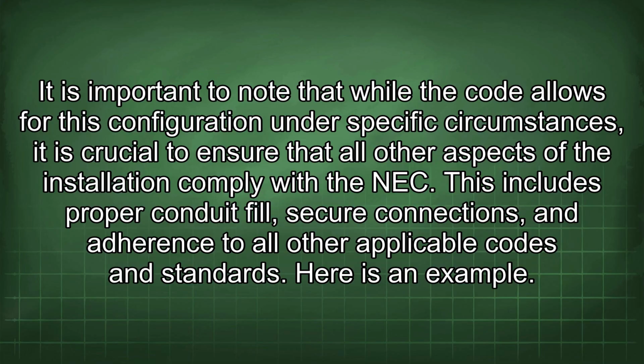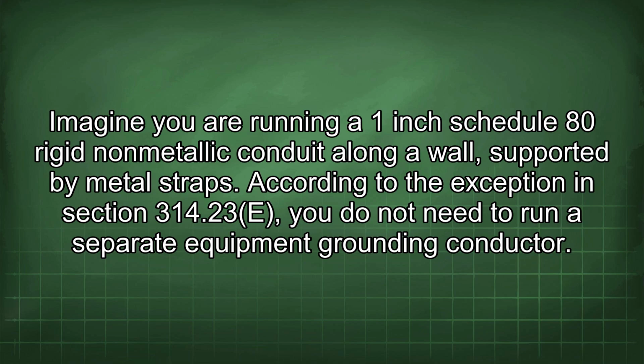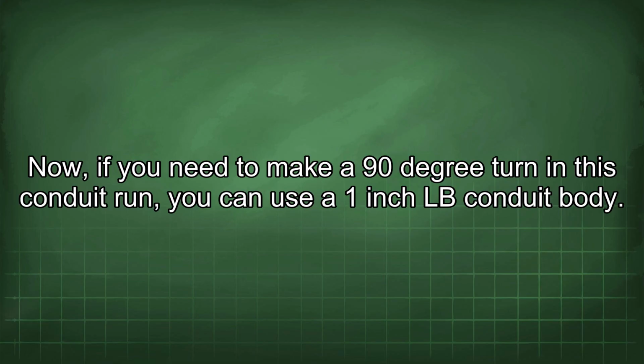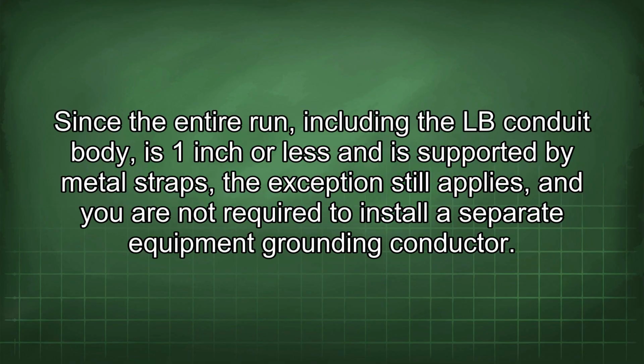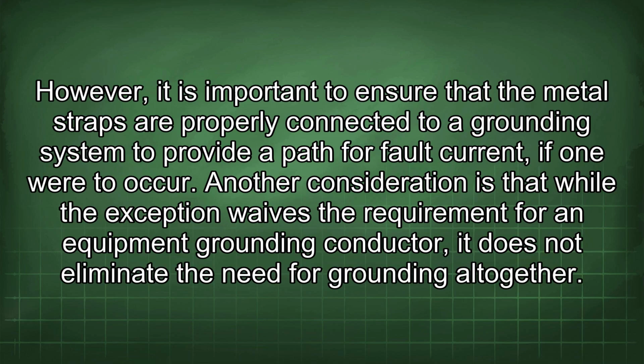Here is an example. Imagine you are running a 1-inch Schedule 80 rigid non-metallic conduit along a wall supported by metal straps. According to the exception in Section 314.23(E), you do not need to run a separate equipment grounding conductor. Now, if you need to make a 90-degree turn in this conduit run, you can use a 1-inch LB conduit body. Since the entire run, including the LB conduit body, is 1 inch or less and is supported by metal straps, the exception still applies, and you are not required to install a separate equipment grounding conductor. However, it is important to ensure that the metal straps are properly connected to a grounding system to provide a path for fault current, if one were to occur.